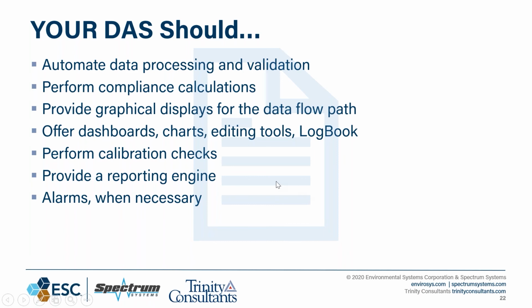The DAS should be the one-stop shop, and in some cases that might not be possible because of SCADA, gas chromatograph. Maybe there's a limitation for how you can get your communications from point A to point B at the plant. But even then, there should be an import function, and you should be able to utilize your DAS if there's something that's remote that you can't get to. Most of these dashboards for DAS can be built out to put together an entire alarm screen. So best practice is if your DAS offers a dashboard, use it and build it and create the screen and put it in the control room.